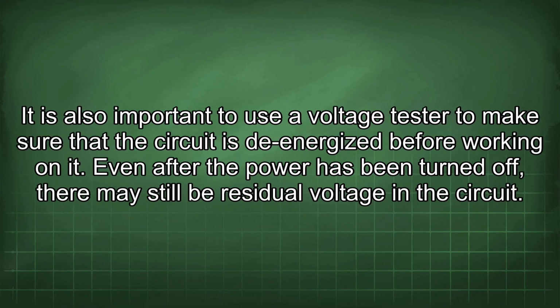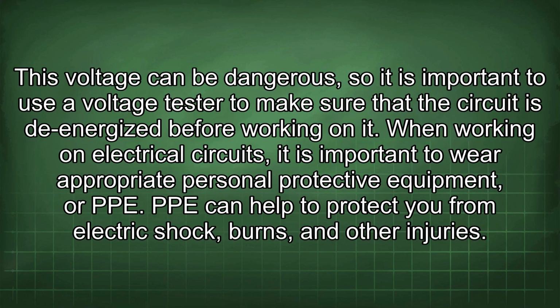It is also important to use a voltage tester to make sure that the circuit is de-energized before working on it. Even after the power has been turned off, there may still be a residual voltage in the circuit. This voltage can be dangerous, so it is important to use a voltage tester to make sure that the circuit is de-energized before working on it.